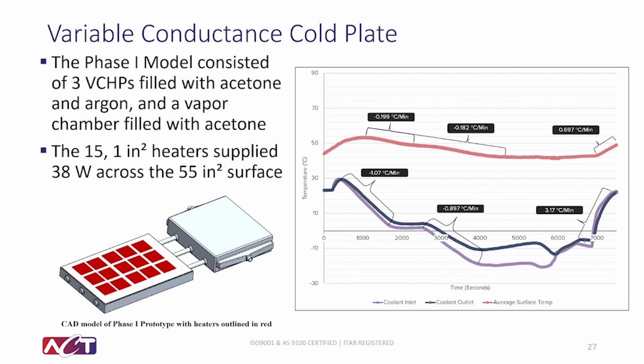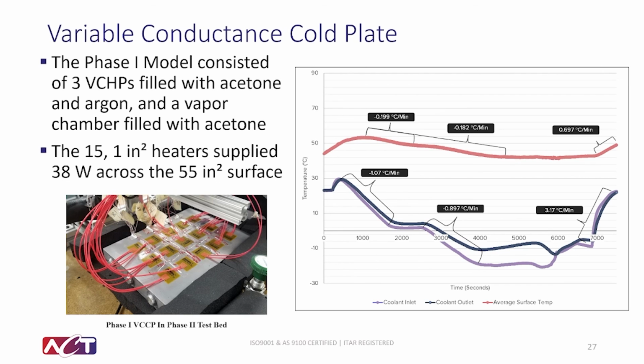We supplied a constant heat load of 38 watts to the heat collection surface, which was accomplished using 15 1-inch squared heaters across the 55-inch square surface. And you can see in this image the prototype for the phase 1. Looking at the graph to the right, we can see that despite rapid temperature changes in the coolant, the heat collection surface was very slow to react. I'd also like to comment that the spatial isothermality was held to be less than 2 degrees difference across the surface of the cold plate.